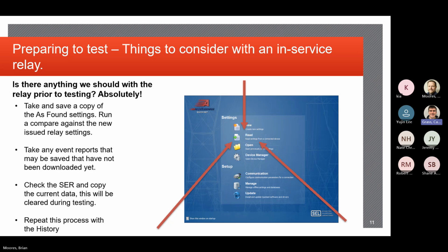So just an FYI. Does everyone understand what SER is, or what a sequential events recorder is in an SEL relay? I think I get it. One question: is it time stamped? Yep, correct. An event report in an SEL relay is generally a series of information from an actual trigger event. If there was a fault on a system, it will log pre-fault time, your currents, voltages, digital inputs, whatever, and put it all in one big event report file. Sometimes you see them as CEV files, some of them you hear COMTRADE. So it's an actual event file all wrapped up.